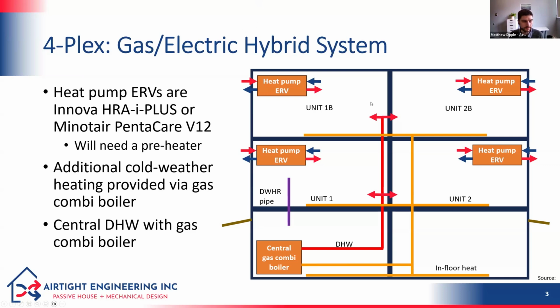My first proposal is a hybrid system where we use combined heat pump ERVs in each suite for cooling, fresh air, and some heating of the supply air. As backup heat, we'd have a central gas combi boiler doing in-floor heat to carry the heating load in cold weather, and it would also provide domestic hot water centrally.